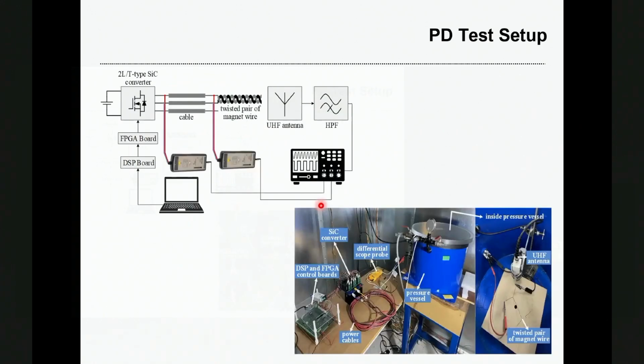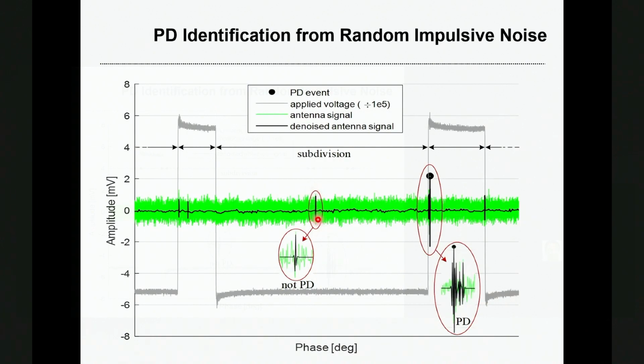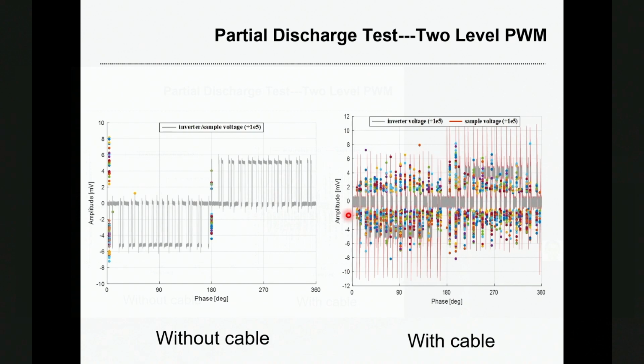And we have measured the partial discharge events in experiment with a silicon carbide converter driving a twisted pair. And we have detected the PD events and put that in the phase diagram with the voltage waveforms. For example, this is with a two-level converter without any cable connected between the inverter and the twisted pair. You can see there are only PD events, partial discharge events, when the polarity of the pulses changes from negative to positive or from positive to negative. And if there is a cable between the inverter and the twisted pair, then there will be overvoltage at the twisted pair. And as you can see, there will be more PD events almost at every switching transition.